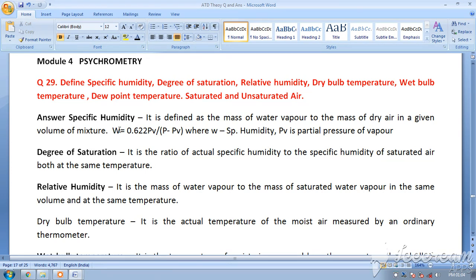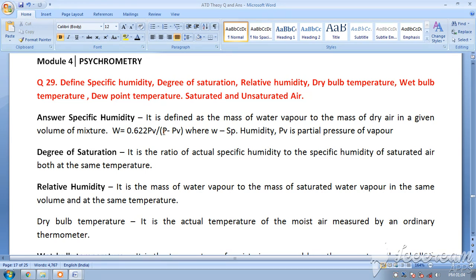The formula for specific humidity is: omega (ω) = 0.622 × Pv divided by (P − Pv), where P is the total pressure of the air, Pv is the partial pressure of water vapor, and omega is the specific humidity. The total pressure P equals Pa plus Pv, where Pa is the partial pressure of dry air. The units of specific humidity are kg of water vapor per kg of dry air.